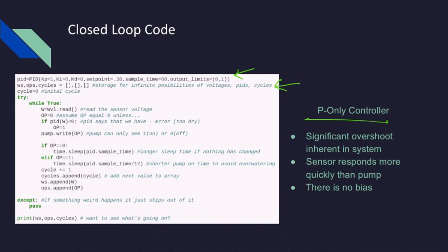We have our PID controller and our cycles, and we decided to use a P-only controller because when you input water into the system, it has a huge overshoot, and we can't effectively take out water, so our error is really big and we can't effectively use an integral term. So we just used a P controller, and that ended up working really well.